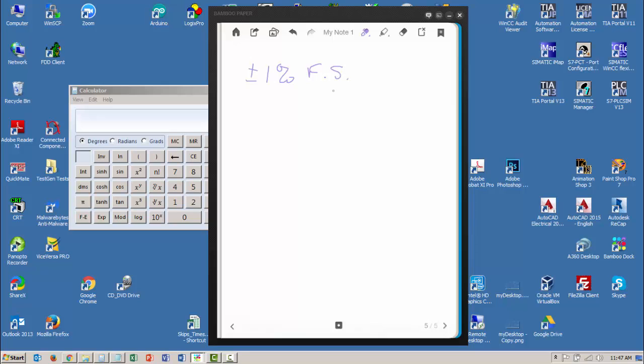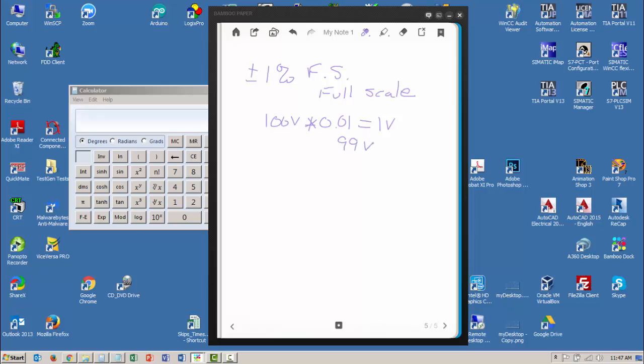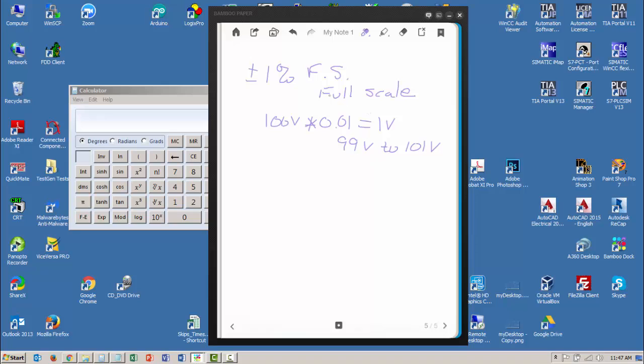And F.S. is full scale. This is going to make some differences. Let's use the same voltmeter and we'll use that 100-volt range again. And we're going to measure 100 volts. Well, at 100 volts, which is full scale, times the 0.01 or the 1%, we know it's 1 volt, and our readings can be between 99 volts and 101 volts and still be in spec.